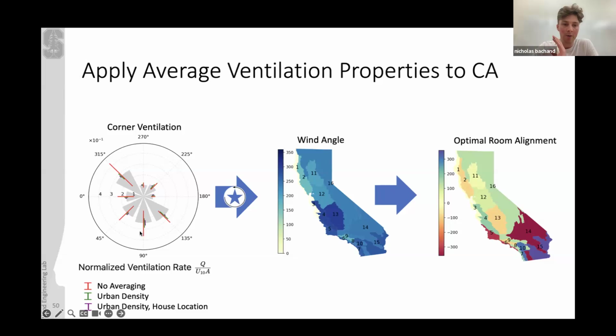This is for all of these wind directions, showing the degree of ventilation we're expecting. There's still a pretty high degree of uncertainty because I'm averaging across urban densities, shown by these red bars. But I can look at the wind roses in all the climate zones across California and match them with these ventilation roses to get optimal alignments of the rooms. On the right of this slide, I'm showing the different angles at which these rooms should be rotated to get the most ventilation. The negative angles are a proxy for first mirroring the room and then rotating it.